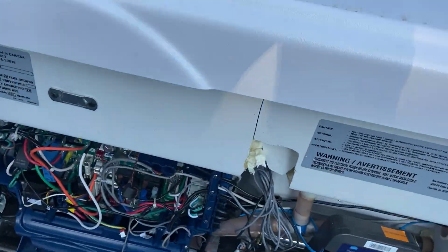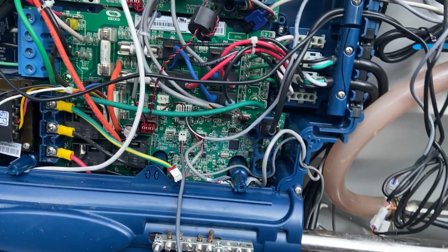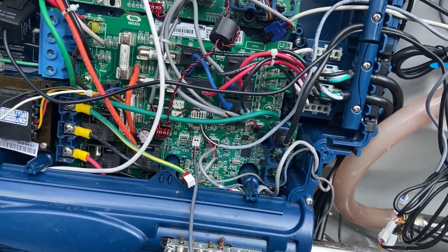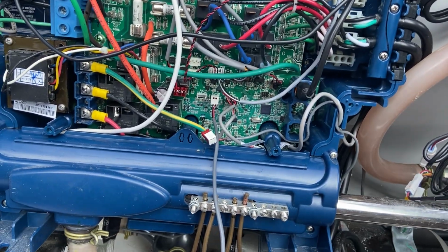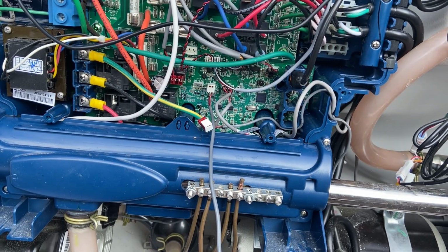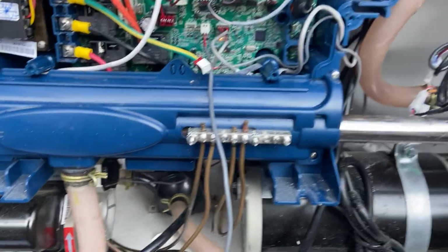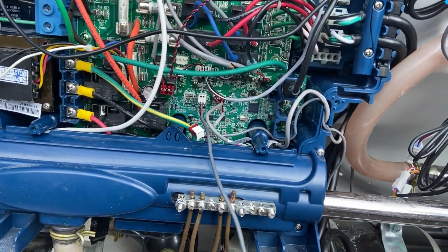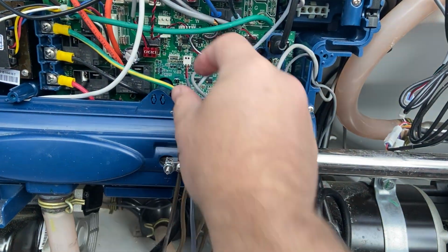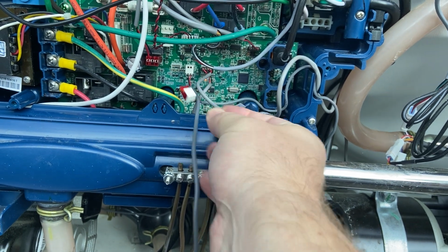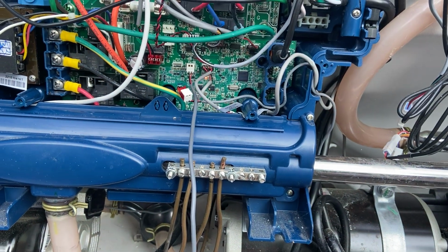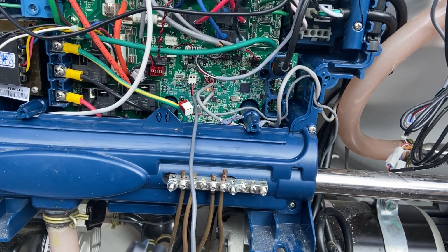So maybe if we were a technician or customer looking at this, the error we might start with is either the flow switch or the board. Now the easiest thing to replace and test is a flow switch here. So the first thing we're gonna do is, remember this is installed, so if I was using my installed flow switch, which I unplugged right here, I couldn't do this testing, but I do want to simulate this testing to show you what happens.